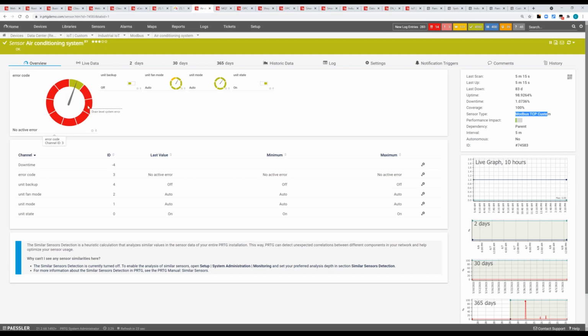Maybe it's a drain level system error, so this is something I might fix myself, I just go there and empty the tank. But when I have another thing, like an overcurrent of an AC input, it's important for me as an admin, because with the overcurrent I wouldn't fix it myself. I would rather inform our electrician, hey, you should go there, the air conditioning system is not running, it may lead to overheating of our industrial cabinet, you should fix it. So you can really pinpoint the root cause by monitoring it.